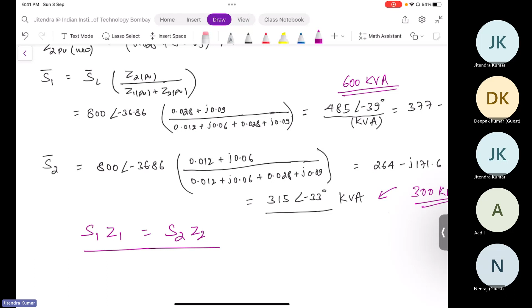And this transformer is overloaded by 5%. How am I saying it is overloaded by 5%? Because 300 kVA was its rating and it supplies 315, so 15 kVA out of 300, which is 5%. So it is overloaded by 5%, and its per unit impedance is also very high compared to the first one. If you see, per unit impedance is high compared to this one. So that has to happen. In such a case, S1Z1 is higher than S2Z2, because this 300 kVA is the second transformer. So it has to happen.